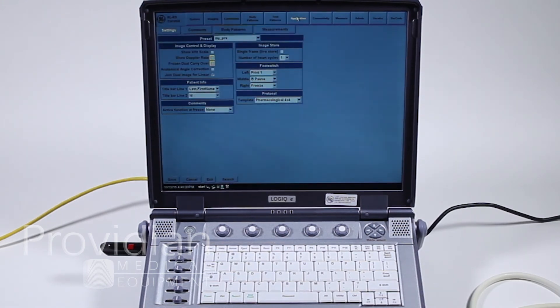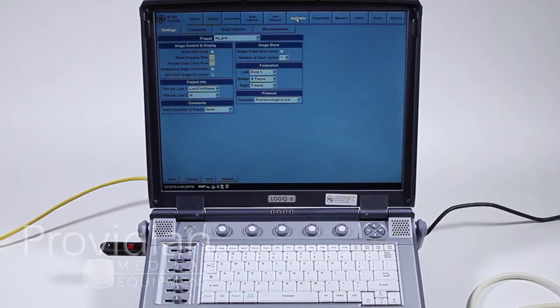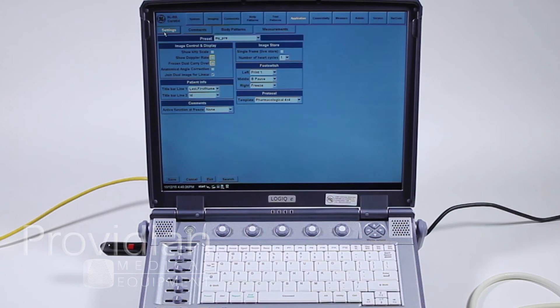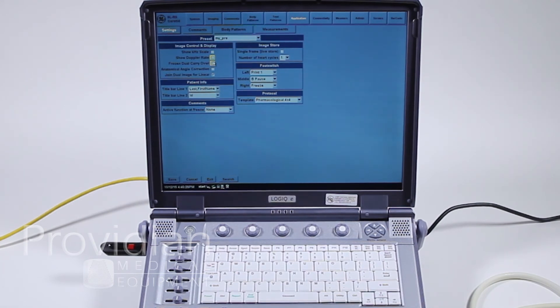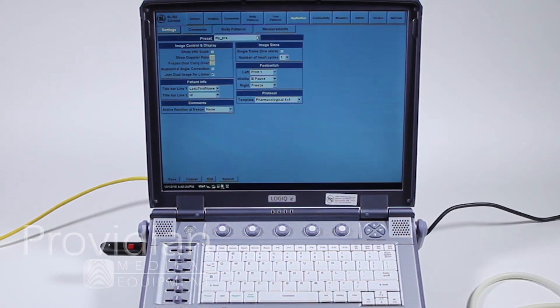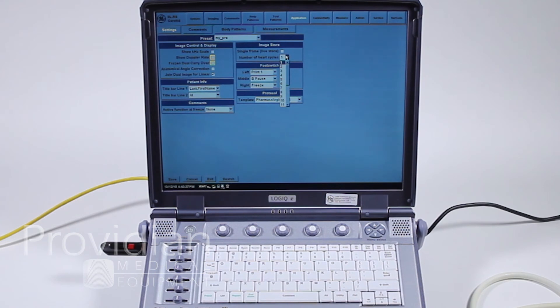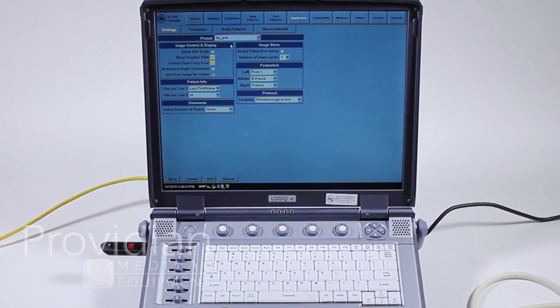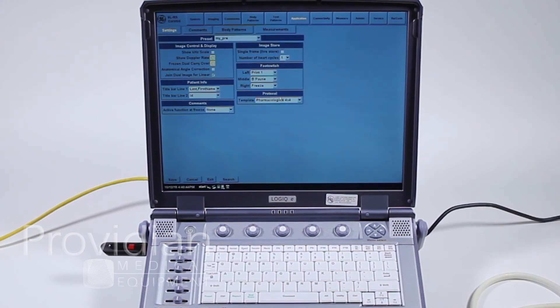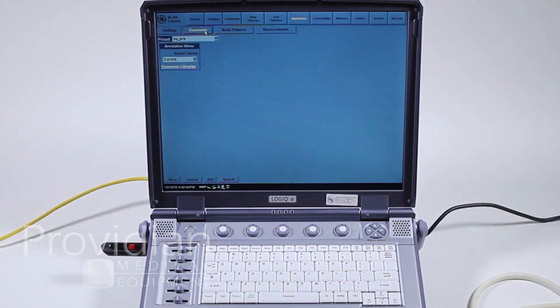Application. This is, we'll go to the settings. This just shows you different things that you can show on screen when you are in a certain preset. For image store, we set one or multiple heart rate cycles. This is when an ECG is attached. Foot switch. And if there's stress echo, this is where you make adjustments there.